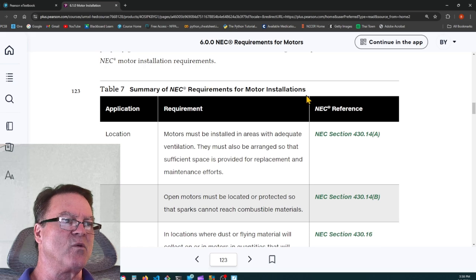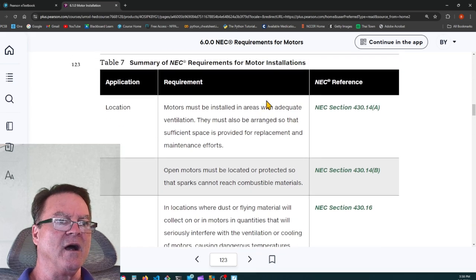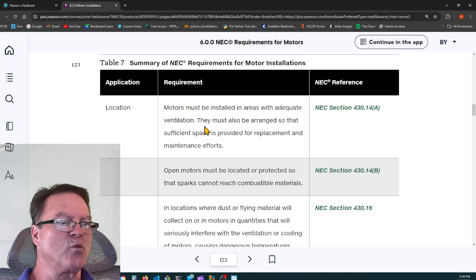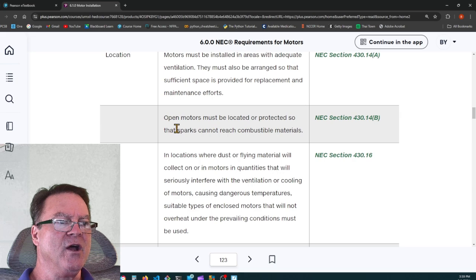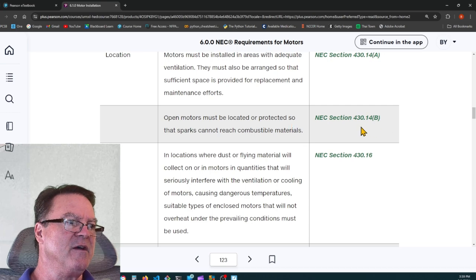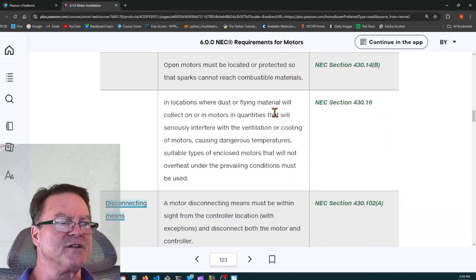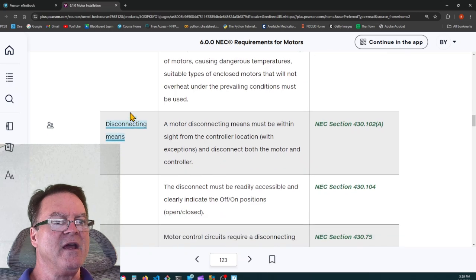So here's a summary of NEC requirements for motor installation. The motors must be installed in areas with adequate ventilation. They must also be arranged so that sufficient space is provided for replacement and maintenance. 430.14(B): Open motors must be located or protected so that sparks cannot reach combustible materials. 430.16: In locations where dust or flying material will collect on or in motors in quantities that will seriously interfere with the ventilation or cooling of motors, causing dangerous temperatures, suitable types of enclosures, enclosed motors that will not overheat under the prevailing conditions must be used.